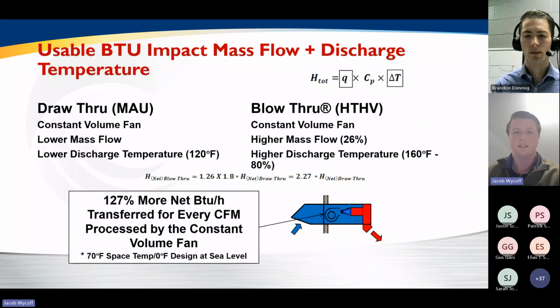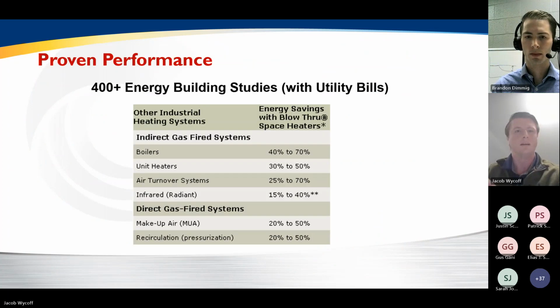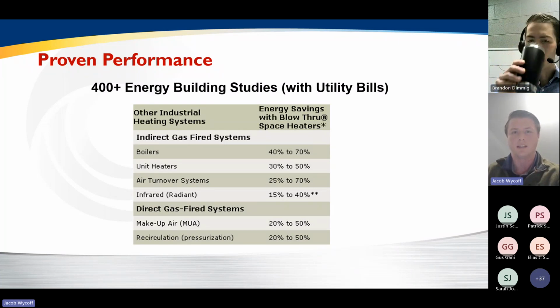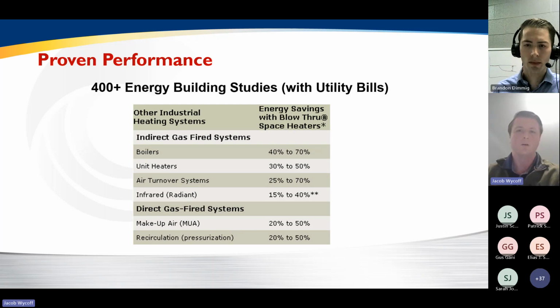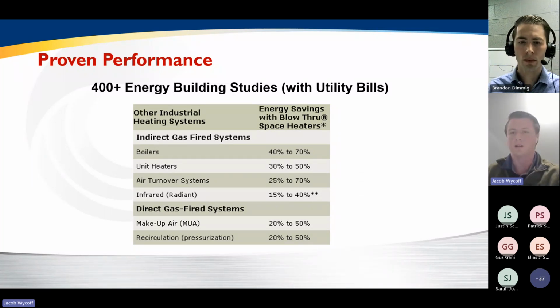So what I said earlier proves out here in the science and the math, but how does that play out in the field or from the examples that we have? Luckily, HTHV is not a new piece of equipment. It's been around for a long time. Cambridge specifically has done over 400 energy building studies with utility bills to back up our claims. So we're going to go through one example here, but reach out to your rep if you're wanting to compare it to an alternate technology or see some more examples or see an energy analysis specific to your building. We have decades of experience comparing these to boilers, unit heaters, infrared radiant heaters, makeup air units, things like that.